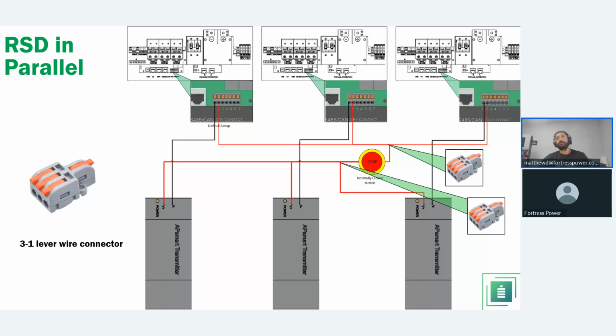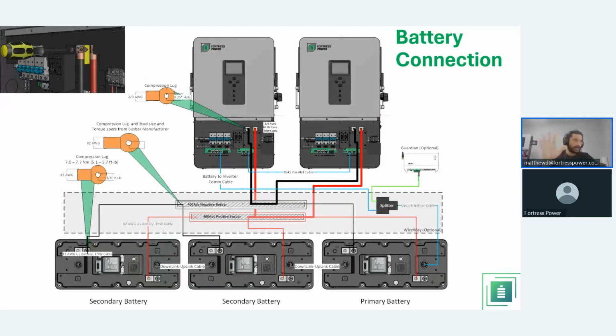And so this will allow you so that when you press the button, everything goes into rapid shutdown mode immediately. Now the rapid shutdown mode is only at a PV level rated for now. It's not going to shut down loads or battery. I know there are some jurisdictions that are mandating a whole system rapid shutdown level. This inverter is not able to do it yet, but we are working towards that. Hopefully we'll have a solution by the beginning of next year.